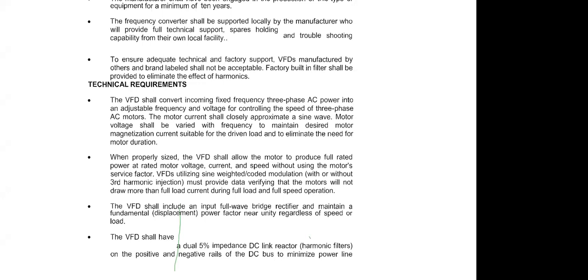So if somebody says that no, the filter is already inbuilt, this is how it is, because this DC link reactor is a part of the VFD. If we ask, still it is available. If we don't ask, still it is available. But total harmonic distortion reduction filters are not available in the VFD unless it is specifically asked for. So here I close. Thank you very much.